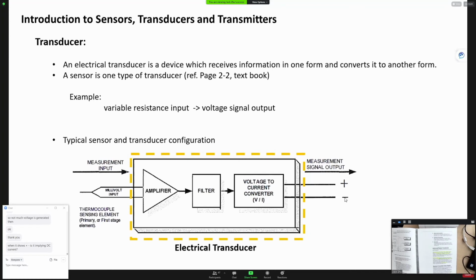Yes, the positive and negative numbers show you this is a DC current. DC current is commonly used in this type of circuit because it can give you not only the amplitude, the number down there, it also tells you the direction of the current flow. You can calibrate this: if measuring at 0 degrees, you will have a positive 4 milliamps, and if the temperature goes below 0 degrees, it might give you a negative current.